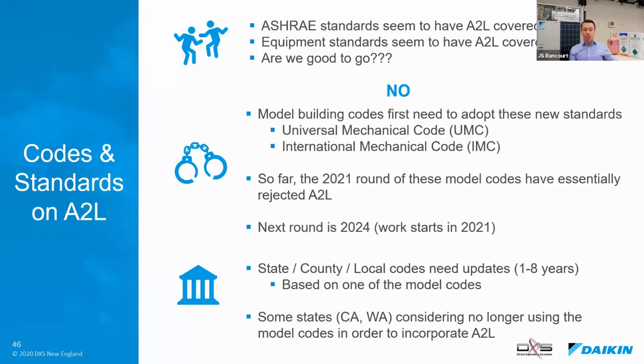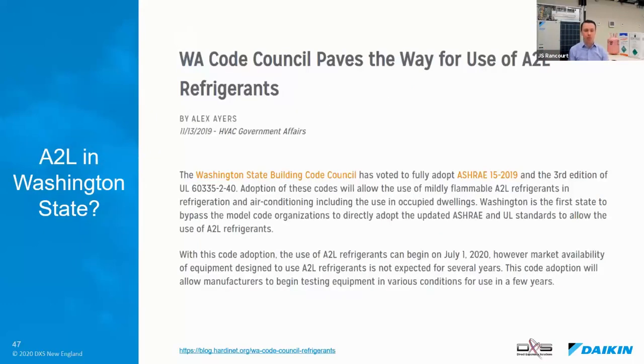For that reason, some states, California and Washington, are considering no longer using these model codes in order to incorporate A2Ls into the building in order to phase down HFCs. Here's an article from last year from Washington saying they have voted to fully adopt ASHRAE 15-2019 and the new UL code. They'll be the first state to bypass the model code to directly adopt ASHRAE and UL standards to allow the use of A2L refrigerants. It'll be very interesting to see.